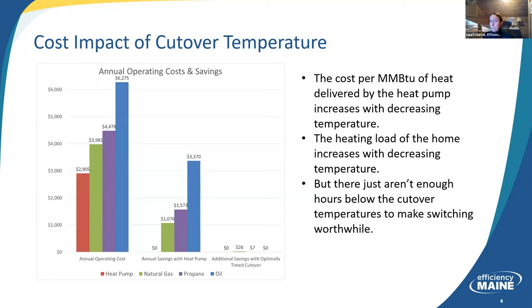And this is really important because we're trying to bust a myth that is out there that you need a backup system and that the backup system has to come on at temperatures well above these cutover temperatures that I just talked about. And I've heard recommendations of 20 degrees, 30 degrees, and switching back over to your old system. With the current costs of energy, it doesn't make sense. It just doesn't. There just aren't enough hours to make it worthwhile to switch.